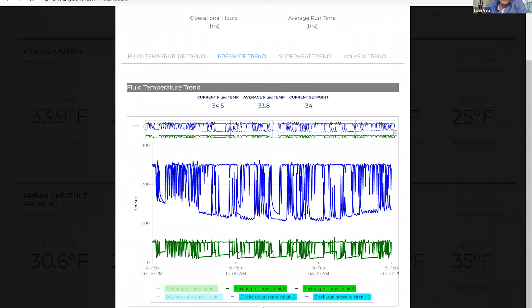We know that unit 3 is operating right now, so we'll look at it. If we only wanted to look at the high pressure side here from the current time at 4 p.m. on February 9th, all the way to the same period of time on February 8th, basically a 24-hour period of time, this is what the pressures look like on that unit, which in that climate with this load is very normal.